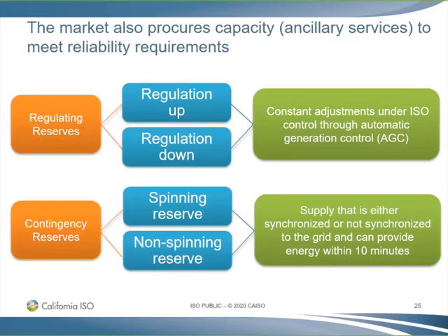So think of these terminology or these titles as having a legacy feel to them. Not necessarily everything is spinning, but the terminology is still used this way. Non-spinning reserves are ones that are not synchronized to the grid, but can be synchronized and be available for dispatch within 10 minutes. Think of fast start generation here.